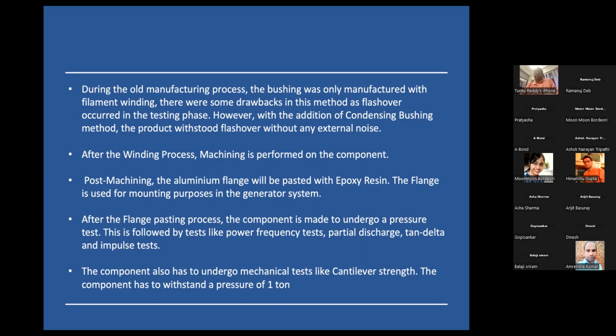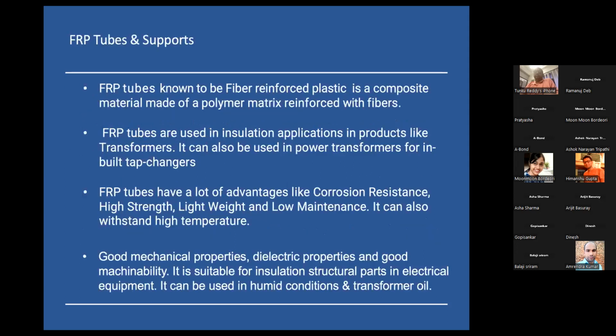After the flange process, we have to undergo all the regular tests like pressure test, power frequency test, partial discharge, tan delta, and impulse test. For the mechanical test, we have to undergo the cantilever strength test and withstand a pressure of 1 ton. Now coming to FRP tubes, my colleague will explain. Before that, I just want to add something.